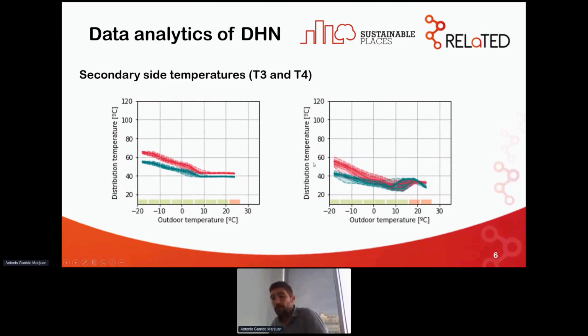Regarding the secondary side temperature on the space heating heat exchanger, we also inspected these 2 years of data entries. On the left is an example of a normal operating district heating substation, and on the right a malfunctioning substation where the response curve is not so good, because the flows were not set as planned—they were operating in an unexpected way.